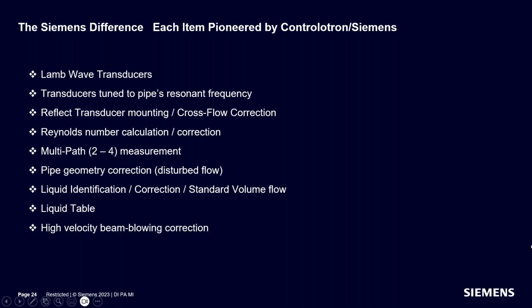And just a brief synopsis of them: Lamb wave transducers were pioneered by Controlotron. Transducers being tuned to the pipe's resonant frequency. Reflect transducer mounting for crossflow correction. Reynolds number calculation and correction. Multipath measurement. Pipe geometry correction or disturbed flow correction. Liquid ID, liquid correction, standard volume flow calculations, liquid tables, and high velocity beam blowing correction. Every one of these things is a part of a Siemens FS230 flow meter. Most, if not all of these, were pioneered by Controlotron.